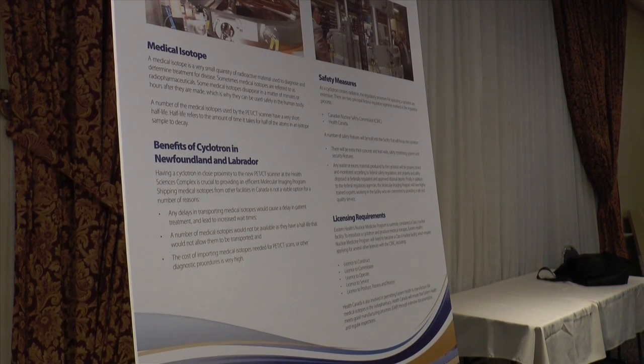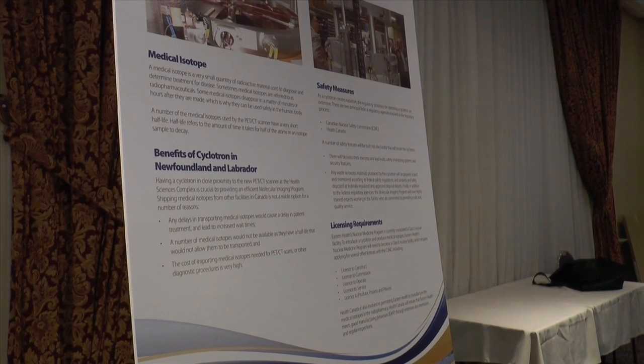A cyclotron is a machine that is a particle accelerator. Basically what happens is you accelerate a proton and it will hit a target. Once it hits this target, it creates FDG, which is going to be the most common PET pharmaceutical that we will produce. So the cyclotron is the means by which we produce it, as opposed to our current medical isotopes where we have to get them shipped in weekly and sometimes daily.